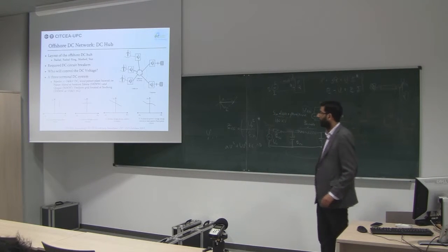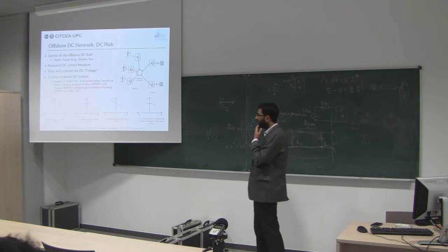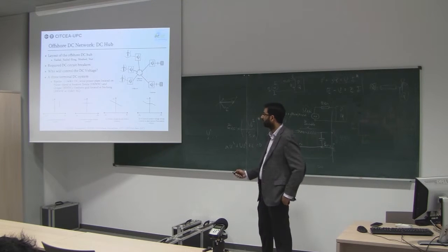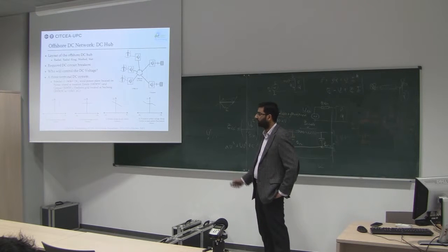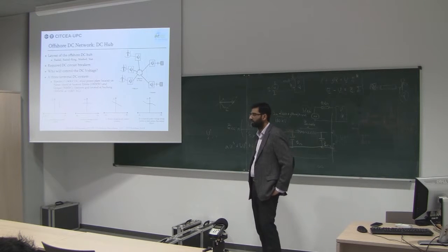I wrote this example from China. I think it's the first multi-terminal DC system, using plus minus 160 kV DC lines, connected to wind farms, one 100 megawatt and the other 50 megawatt, connected onshore at 110 kV with a capacity of 200 megawatt.